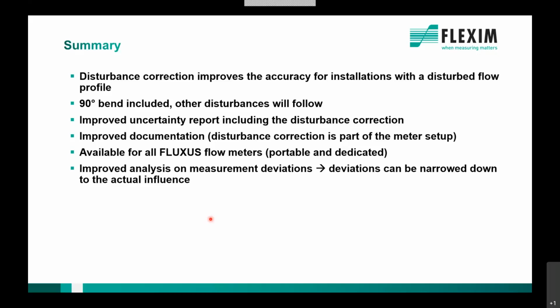Why? Because it's also part of the setup. So in any case, if you want to check what you really compensated, you can do it later anyway and make a calculation out of it. We have an improved uncertainty report, including the disturbance correction, that's what I showed you, and you have improved documentation. As I said, the disturbance correction becomes part of the setup. That means it's documented, you can print the report, and even after years of installation, you still can check what did I actually install and use. It's documented, and as long as you do not delete the files, you have it documented forever.